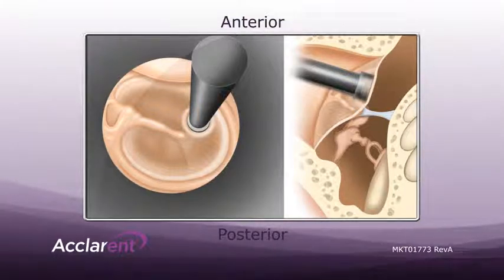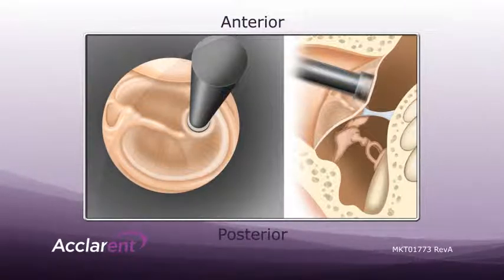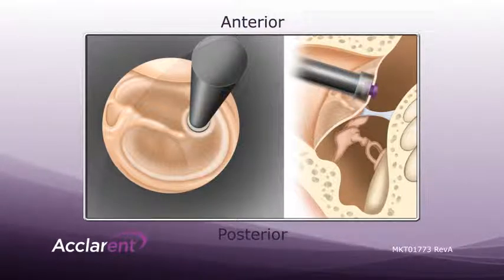To insert the tympanostomy tube, gently press the button while keeping the tip of the device immobile. The device will create a myringotomy and insert a preloaded tympanostomy tube in less than half a second.